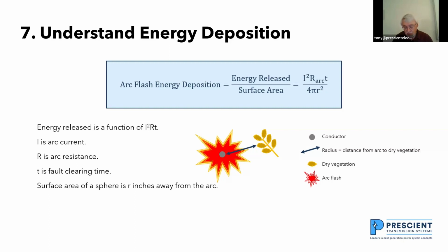The radius of the sphere is from where the arc is occurring to where the dry vegetation is. When I'm doing calculations like this, I make the assumption that the dry vegetation is 2 feet away from an insulator. That gives me the maximum energy that I'm transferring and putting on the surface of burnable material. If you don't have anything that's going to burn nearby, if you're 10 feet away, the energy from an arc flash is a lot less than it is at 2 feet away.